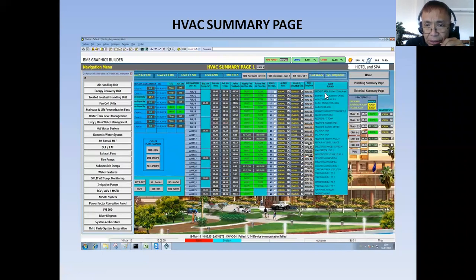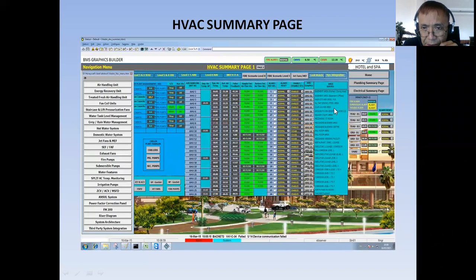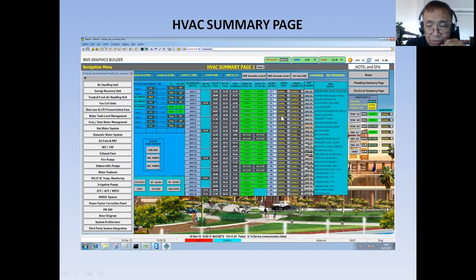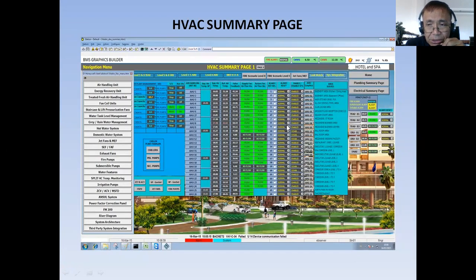I also have the area being served displayed here. I'm doing this because let's say the BMS operator is sitting in front of the BMS workstation and receives a call — someone from the dining room or restaurant complaining that it's a little bit hot. He knows already which air handling unit is serving the dining area, checks it, goes to the graphics of that unit, and can change the set point if it's a little bit high. That's why it's delivering slightly hot air. By sitting in front of the computer, you will be able to know what is happening with your air conditioning system. So this information helps the chief engineer check what is going on in the project.